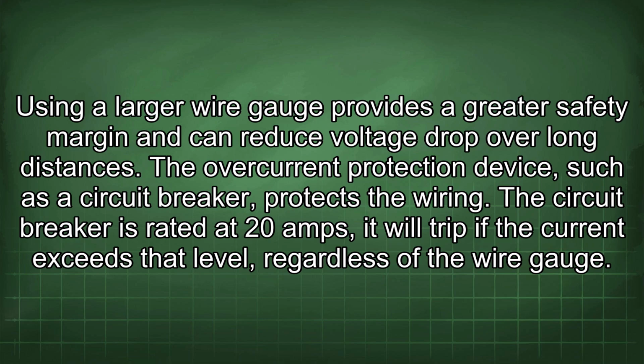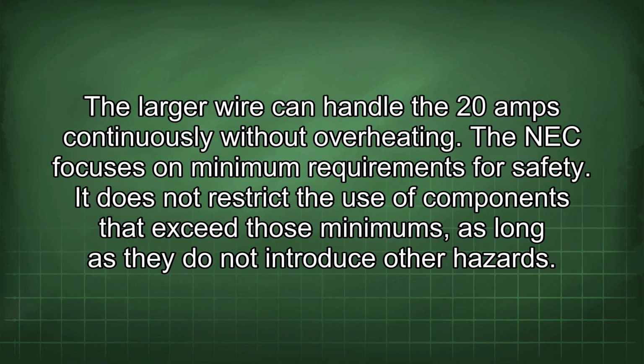The overcurrent protection device, such as a circuit breaker, protects the wiring. The circuit breaker is rated at 20 amps. It will trip if the current exceeds that level, regardless of the wire gauge. The larger wire can handle the 20 amps continuously without overheating. The NEC focuses on minimum requirements for safety.